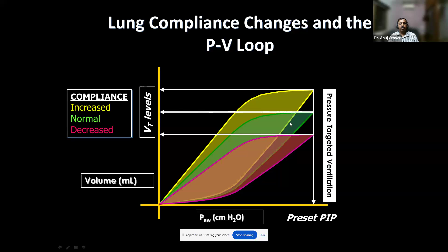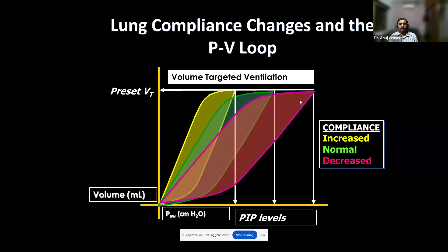If you have it on volume targeted mode, you have set a preset tidal volume. Initially when your baby has RDS, you need higher pressures to achieve the desired tidal volume. Once you've given the surfactant and the compliance improves, you're going to need lower pressures. But if you're on a volume targeted mode, the ventilator will automatically reduce the PIPs. So as the compliance improves in volume targeted ventilation, this PV loop is not going to rise up, it is going to shift to the left.